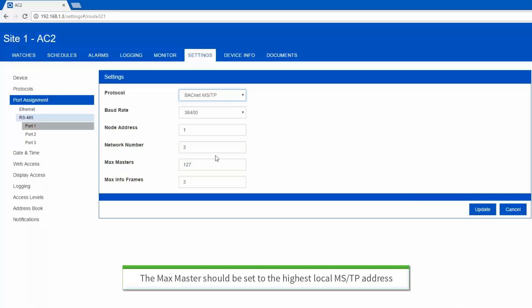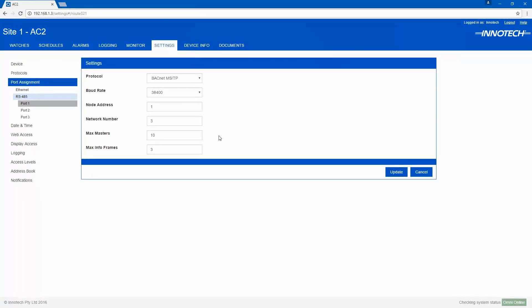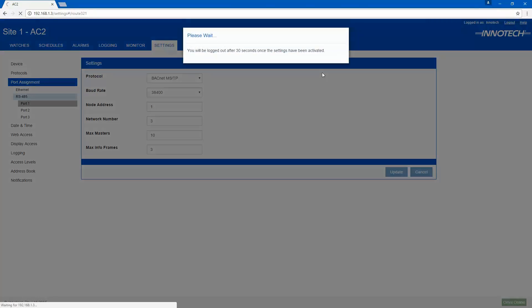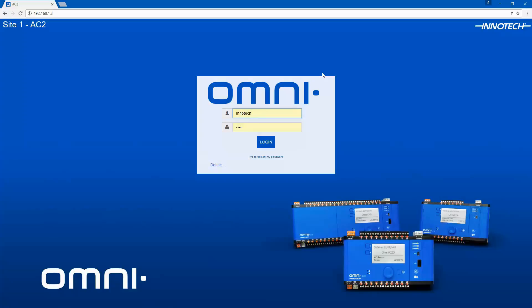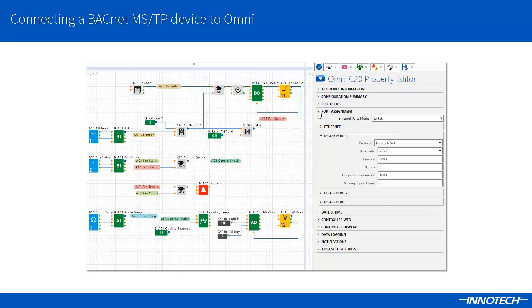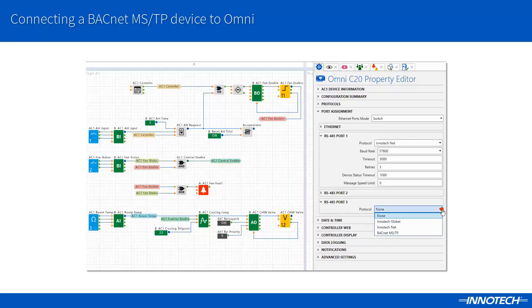To optimize the MSTP link traffic, I can reduce the max masters to a lower number as I only have a few devices connected on this link. For my project, I will set this to 10. Click the Update button and save the changes. Omni will restart and the configuration will be implemented. You can also configure the comm ports in addition to all other Omni settings via Focus. Simply edit the settings for the selected controller, then transfer the updated config.